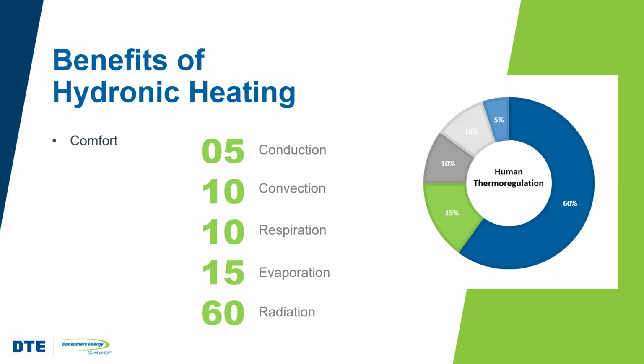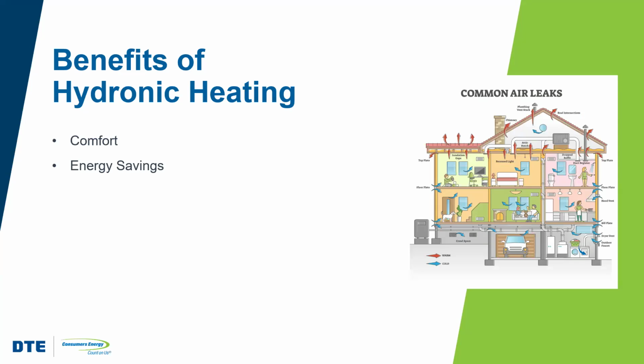conditions. Now, it's worth noting that we would not be comfortable in spaces just because the air temperature is at 70 degrees, which most people think is the ideal temperature, right? Just because the air is at that temperature, if the walls or the windows or the floor were at, say, 60 or 55, we would be uncomfortable, right? And that's because the mean radiant temperature of the space, of the home, is just as important as the air temperature. The hydronic systems help address that. So in some ways, they can provide a more comfortable, more even heat than forced air systems.